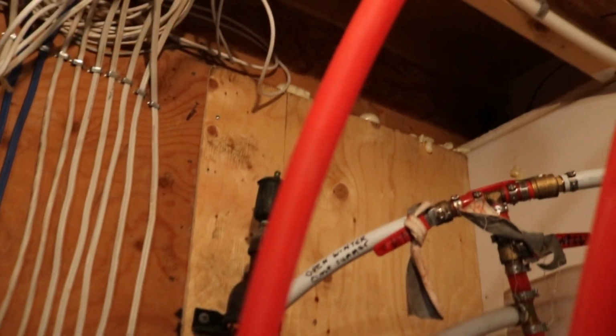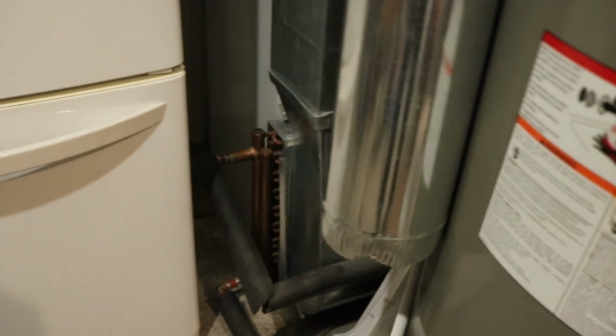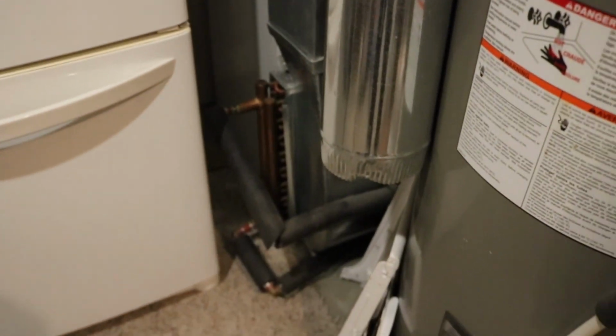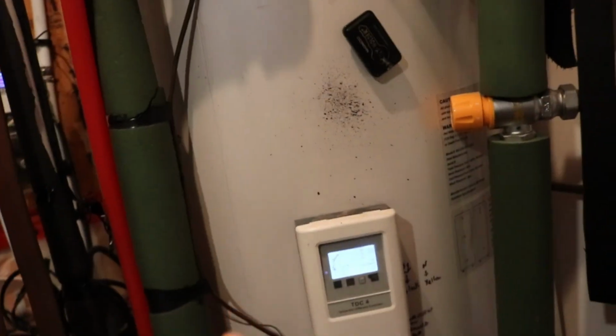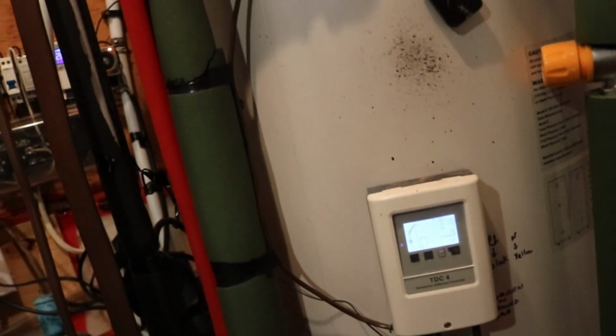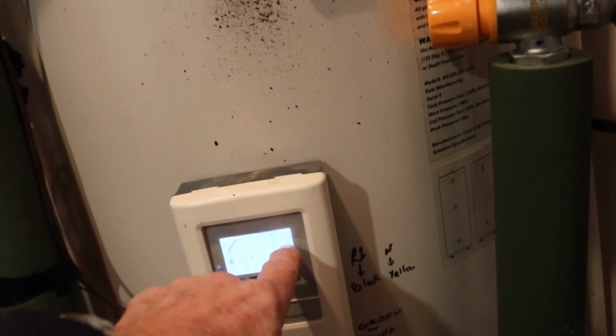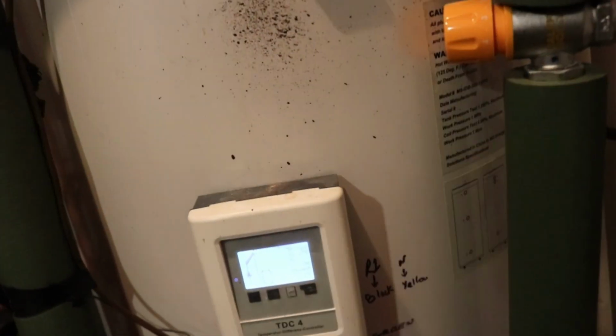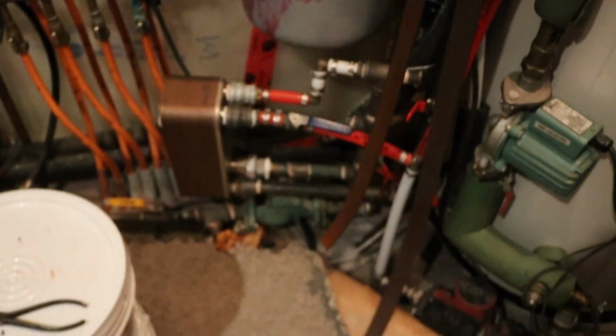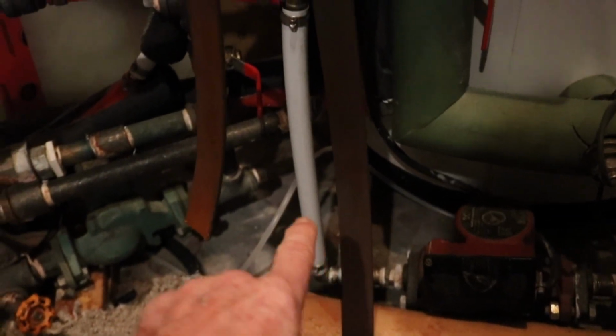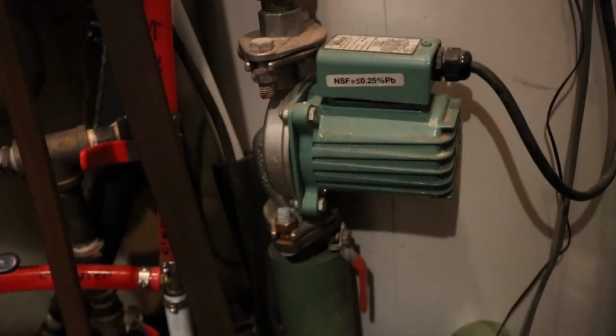So let me show you how this works. The water comes out of the tank here, goes up to the solar panels, comes down here, through here, goes through a rad in the furnace. I leave my fan on all the time, blowing low, blows that hot air up the rad, and then it comes in here in the top. So the water in here now is 27 degrees, and when it's 5 degrees hotter outside than the water temperature, this pump starts the circulation again. Down here I have a plate heat exchanger. You can see it. So it comes out of the tank through the plate exchanger and back up.